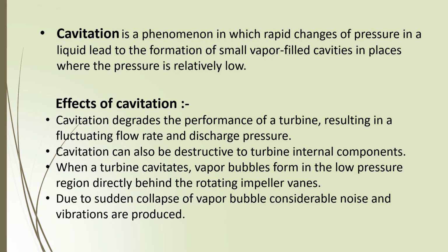So another important effect in this chapter in this turbine is called cavitation. It is a very serious problem in the turbines. So what is cavitation? It is a phenomenon in which rapid changes of pressure in a liquid lead to the formation of small vapor filled cavities in places where the pressure is relatively low. This formation of vapor bubbles is usually called cavitation.